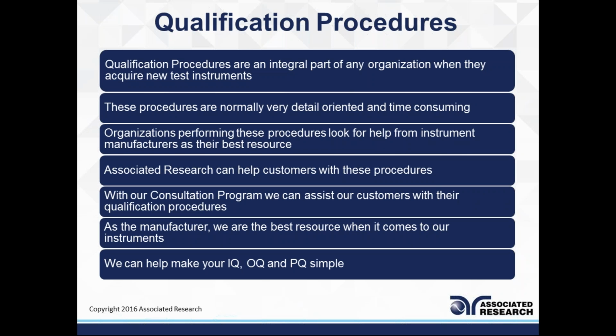But let's look at installation qualification. What is IQ? Well, any new equipment, when it's purchased, or even before purchasing, is first validated to check if it is indeed capable of producing the desired results through design qualification. That's another type of qualification procedure, design qualification, and it's included in the installation qualification. But its performance in a real-world scenario depends on the IQ. Okay, so DQ is design qualification, when you're deciding what's the best fit.